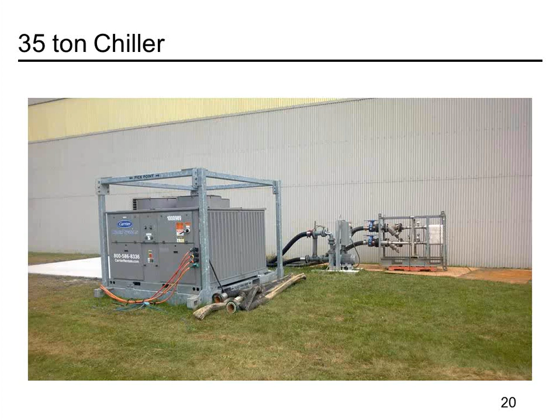Here's an example of a 200-ton air-cooled chiller. Similar situation, you're seeing a chiller to the right. To the left, you're seeing a heat exchanger. It's another plant that had to have the process water isolated from the chilled water loop. Many times, if you're operating a system and they have to have water inside, we're using a similar setup as this, where we have a glycol loop outside for low winter ambient protection, and then the heat exchangers going inside to cool the process water, because they don't want to circulate glycol throughout their plant for many different reasons that could be.